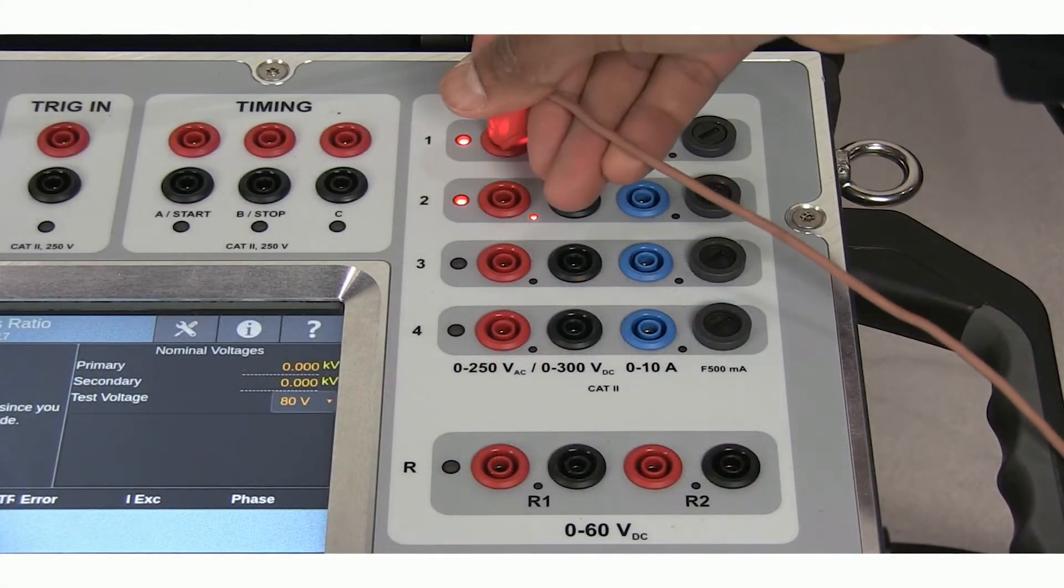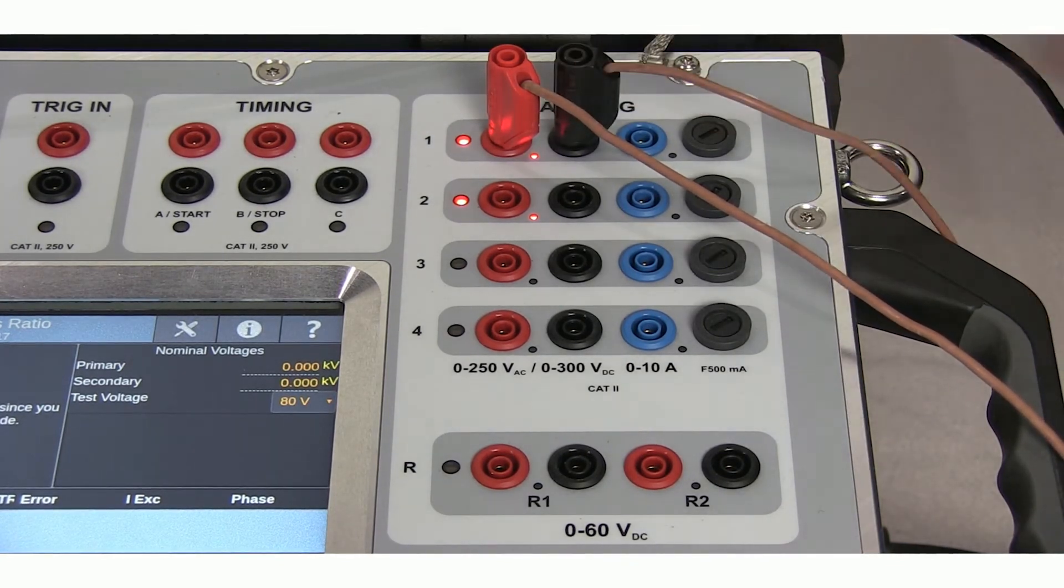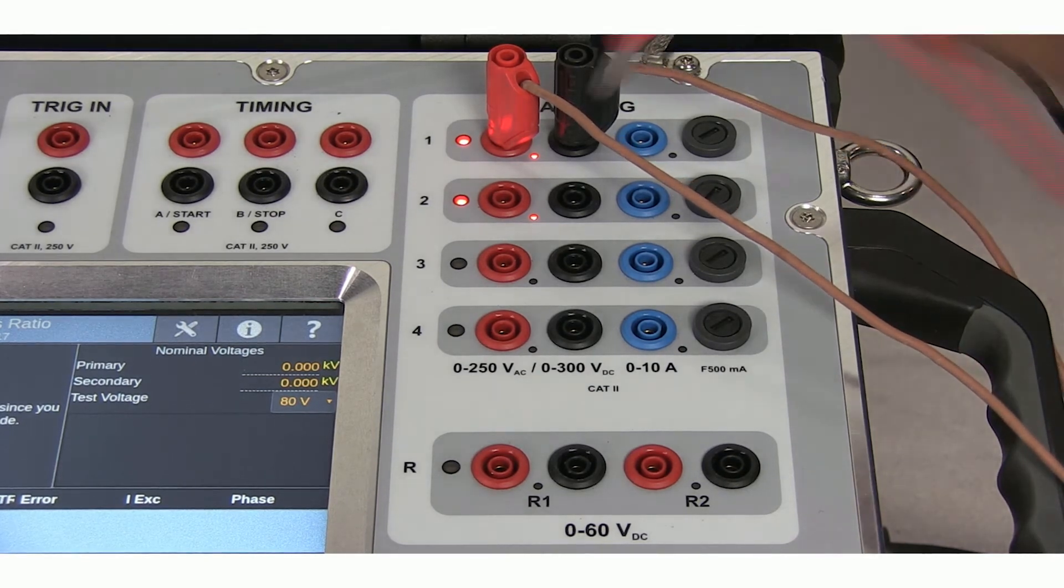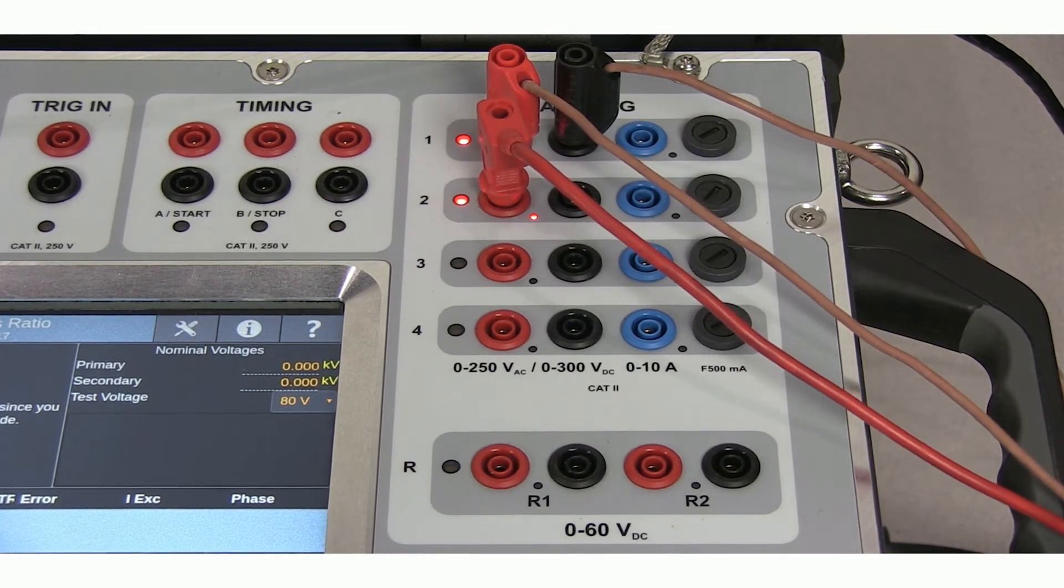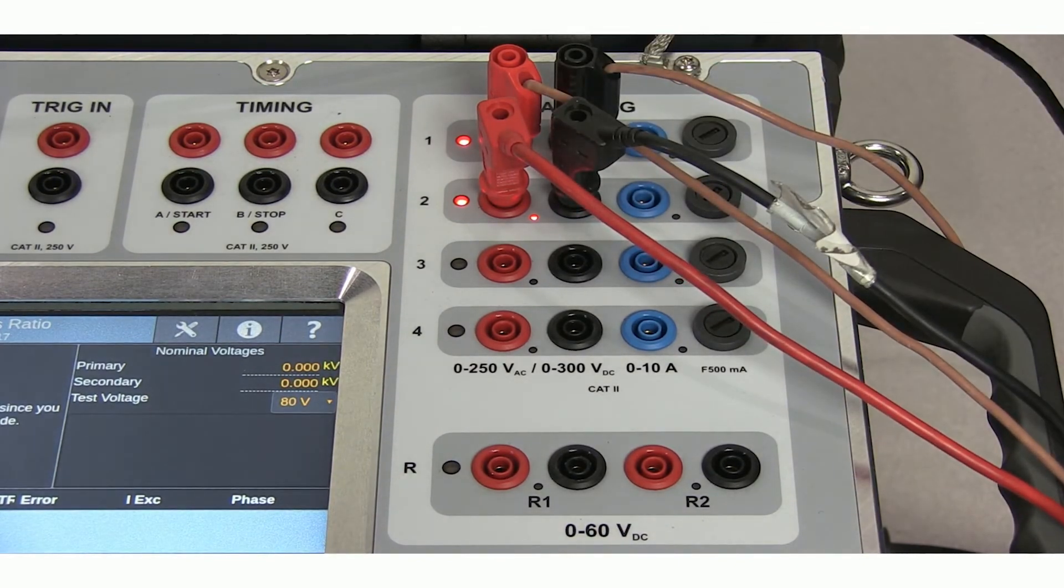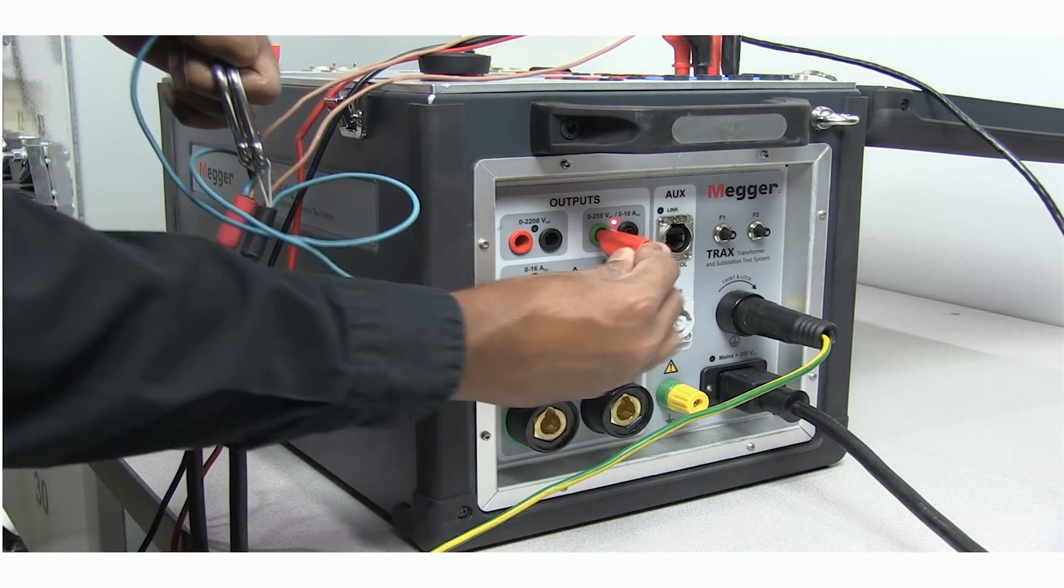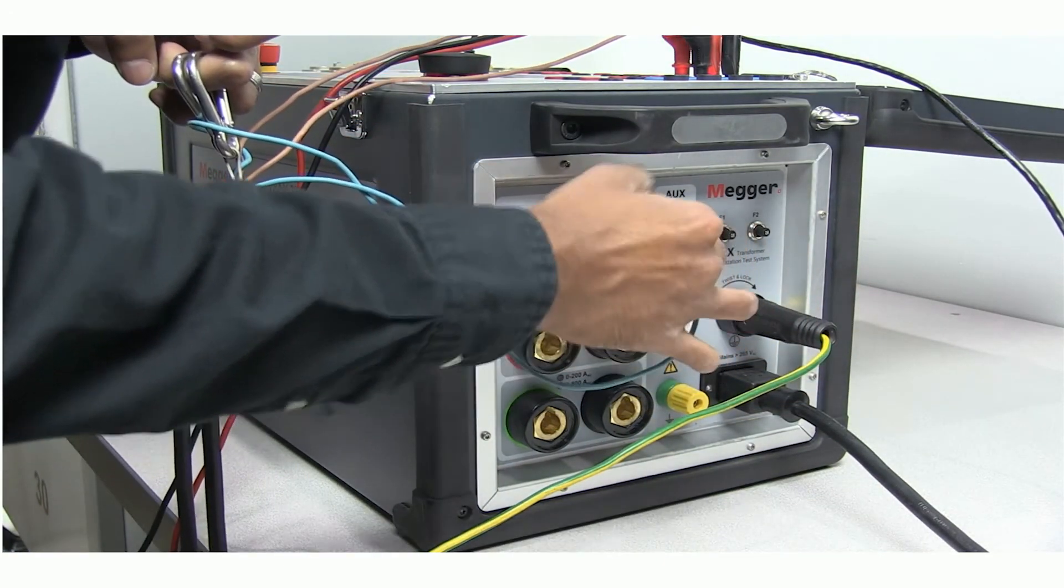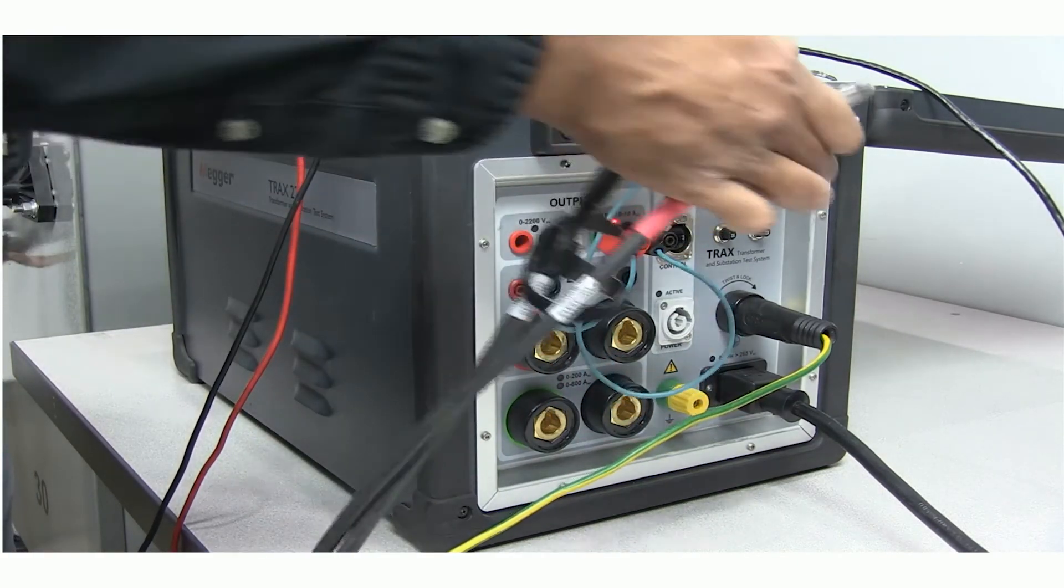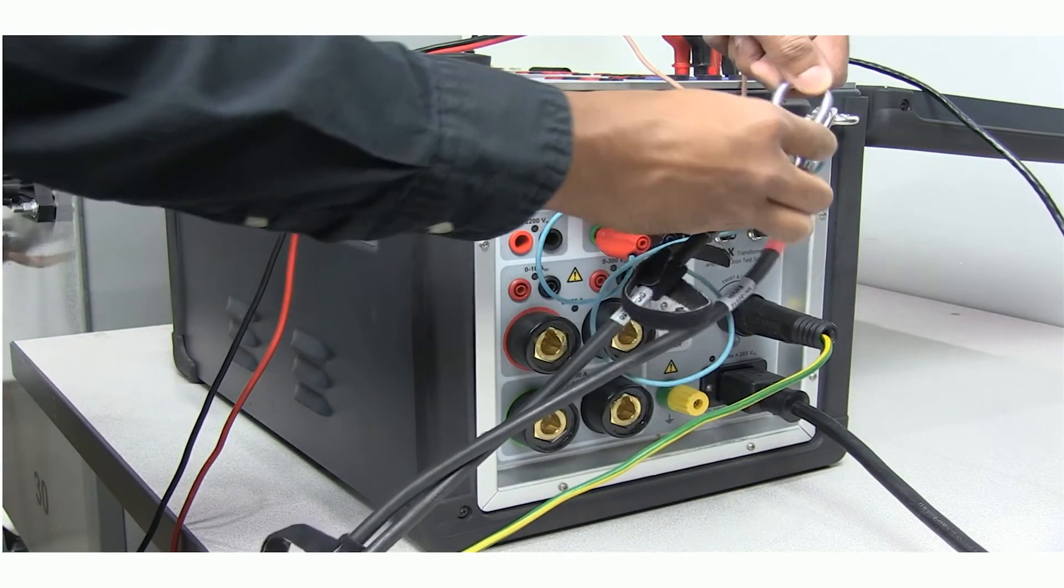When the TTR app is selected, the LEDs for the TTR inputs and outputs light up. Here I'm connecting the measure ends of the Kelvin cables to channel 1 and the sense cables are being connected to channel 2. The generator ends or the power ends of the Kelvin cable are now connected to the TTR output, which is the 250 volt AC source. You can use the strain relievers provided on those cables and hook them up on that little ring provided on the TRAX main unit.